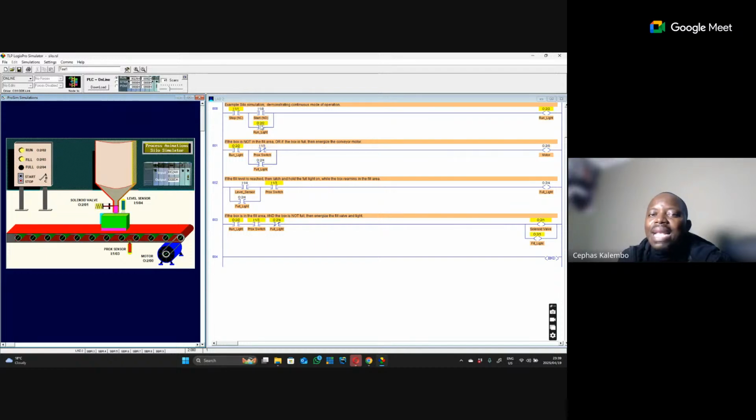Because it's depending on the output register, which can only change after something changes on the input scan cycle, this will be forever on. Only when the output is updated, depending on the changes on the input scan cycle, is this going to change. You have seen that? So this will be forever latched.